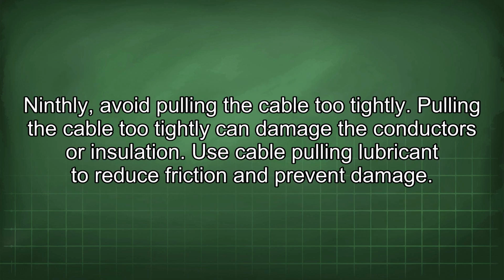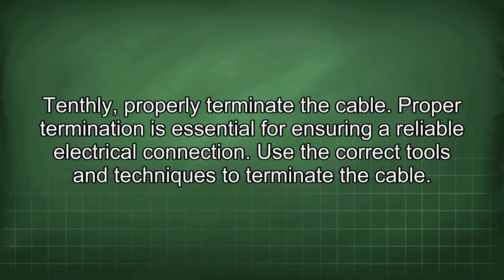Ninthly, avoid pulling the cable too tightly. Pulling the cable too tightly can damage the conductors or insulation. Use cable pulling lubricant to reduce friction and prevent damage. Tenthly, properly terminate the cable. Proper termination is essential for ensuring a reliable electrical connection. Use the correct tools and techniques to terminate the cable.